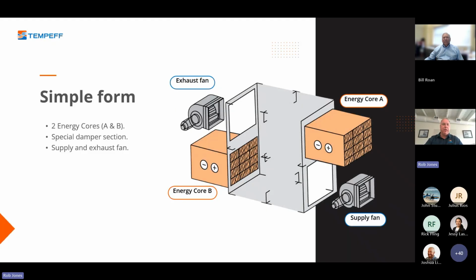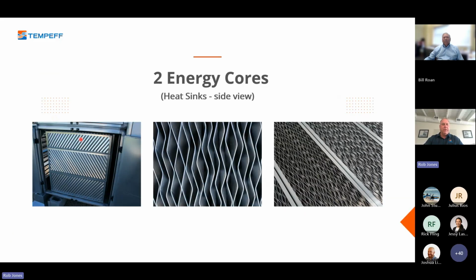In its very simplest form, this is the heartbeat of our unit. We have an exhaust or return fan, a supply fan, 2 aluminum energy cores, and a damper changeover section in the center. This is it in its simplest form. The energy cores are made up of aluminum. We do it in a cassette style fashion, and it's directly related to the amount of CFM that is going through the unit. This cassette in the middle is the biggest one we make.